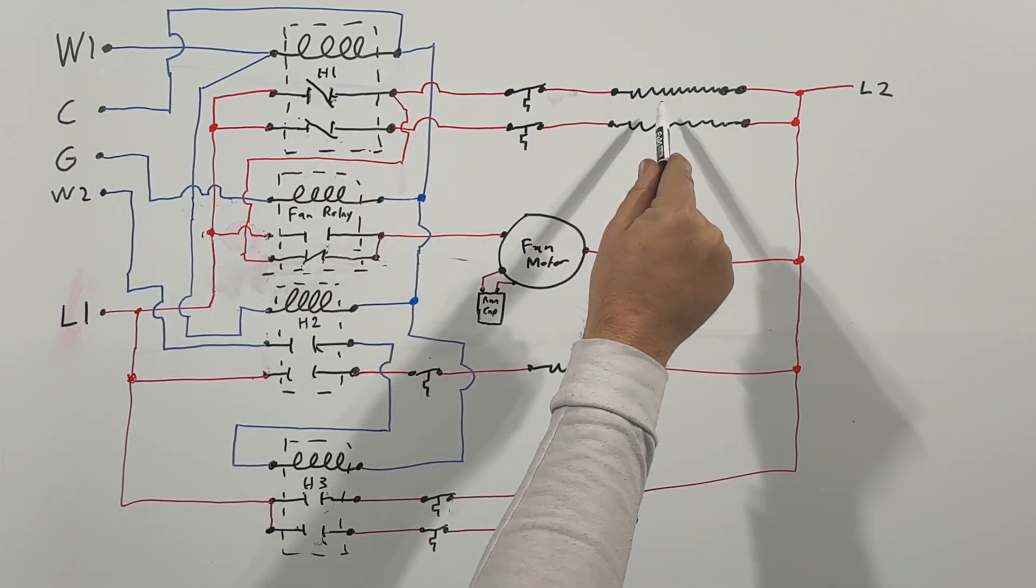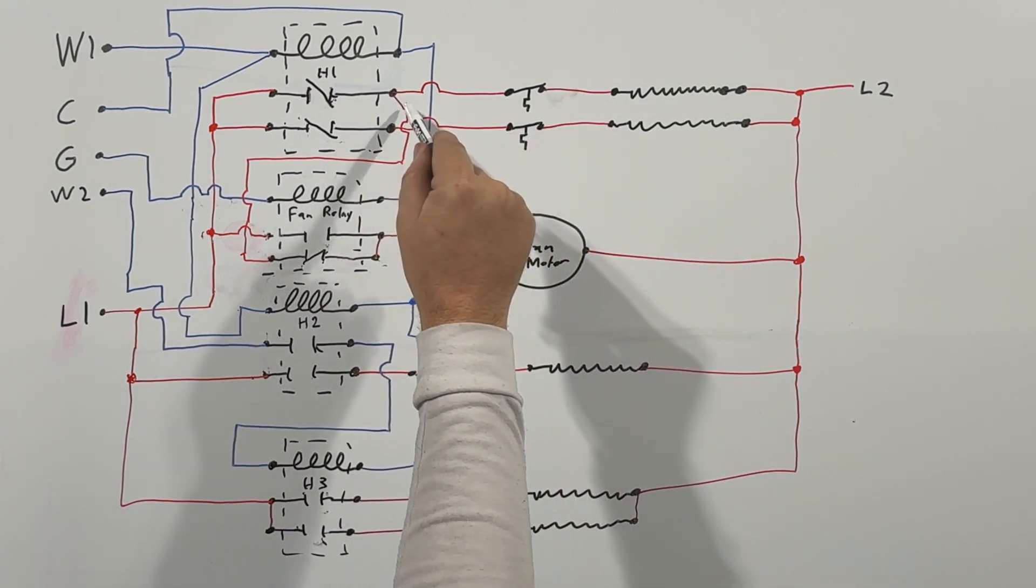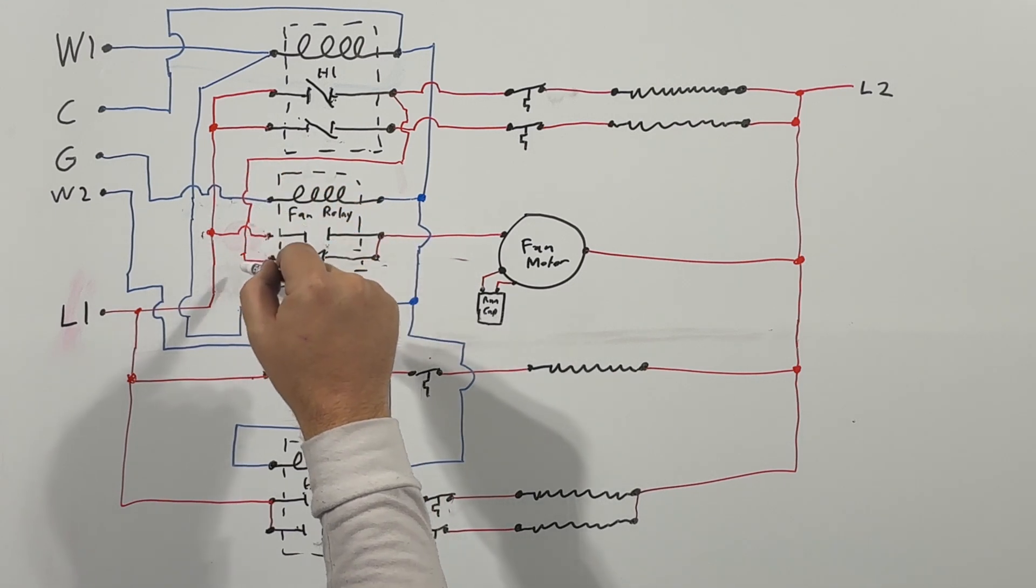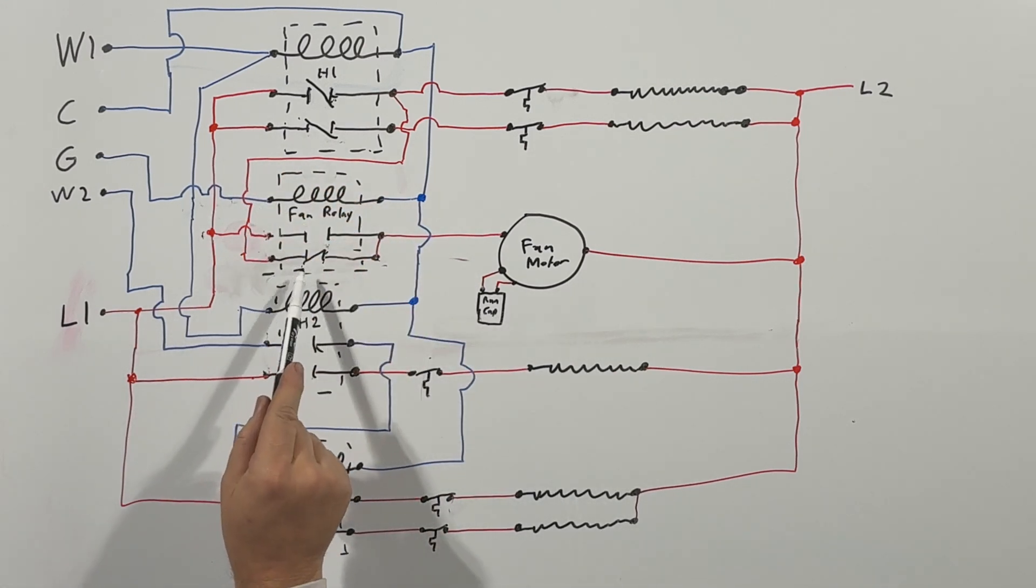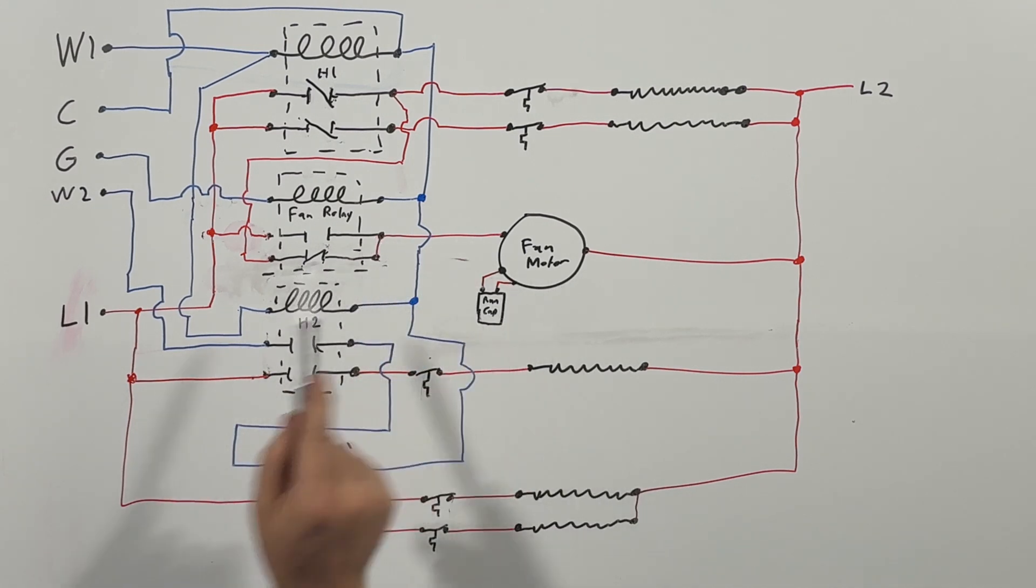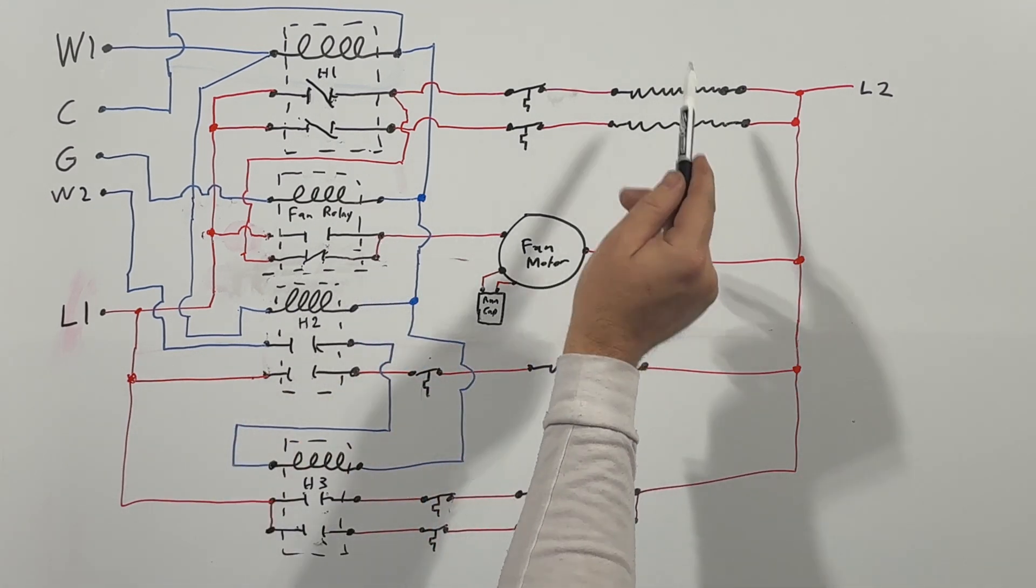And that's going to go into our normally closed contact. So high voltage will go through that contact and then go to our fan motor, which will energize the fan motor and that first strip at the same time.